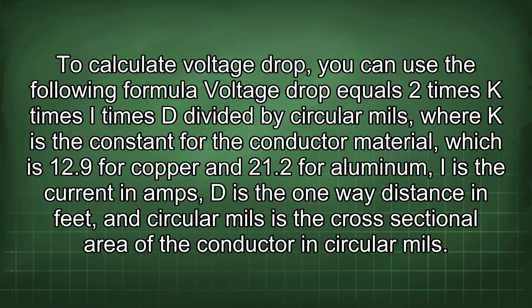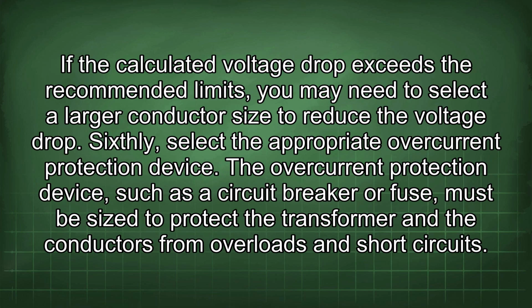To calculate voltage drop, you can use the following formula: voltage drop equals 2 times K times I times D divided by circular mils, where K is the constant for the conductor material, which is 12.9 for copper and 21.2 for aluminum. I is the current in amps, D is the one-way distance in feet, and circular mils is the cross-sectional area of the conductor in circular mils. If the calculated voltage drop exceeds the recommended limits, you may need to select a larger conductor size to reduce the voltage drop. Sixthly, select the appropriate overcurrent protection device.